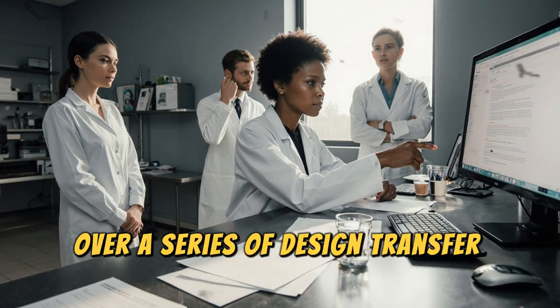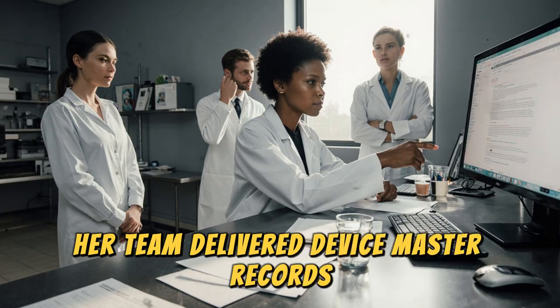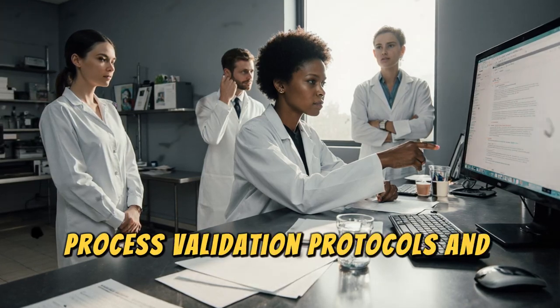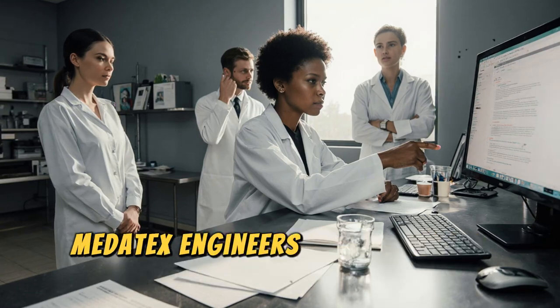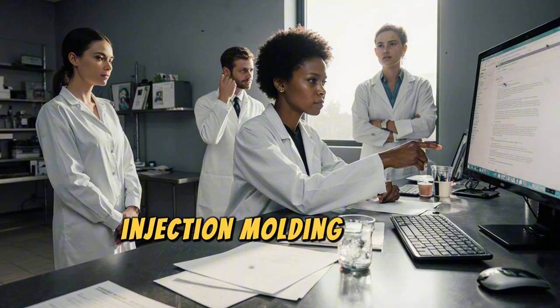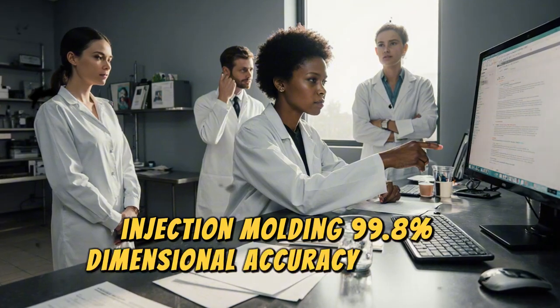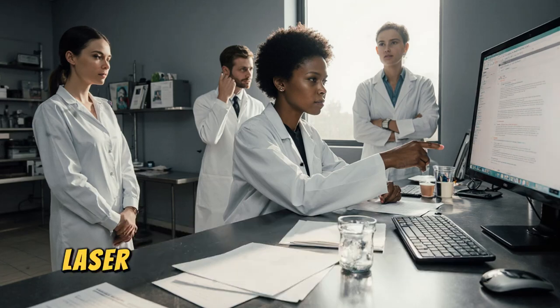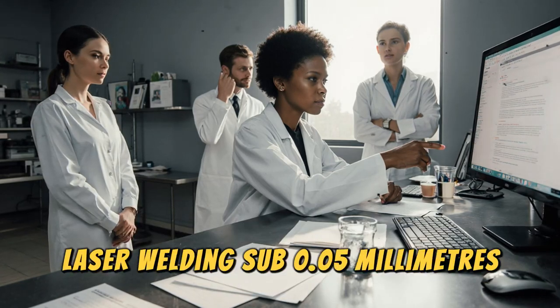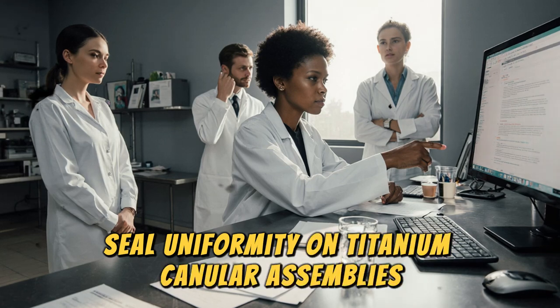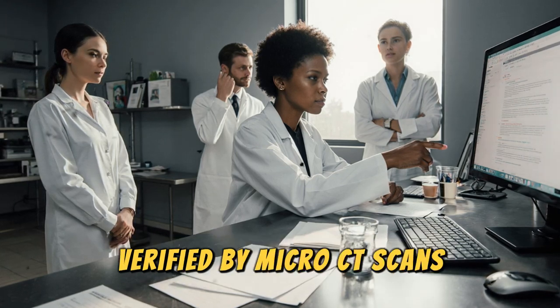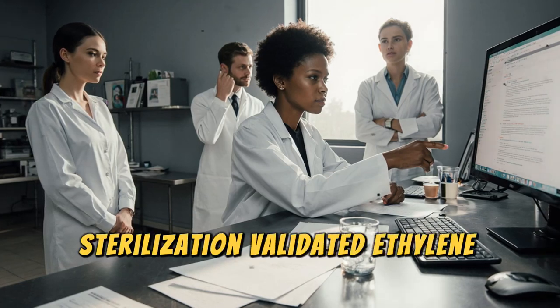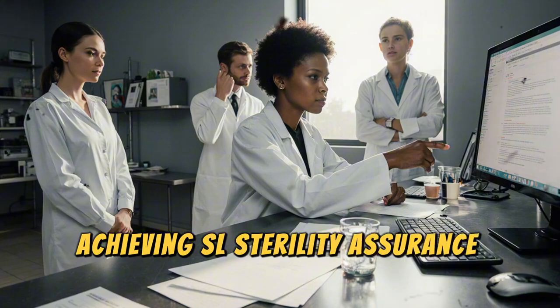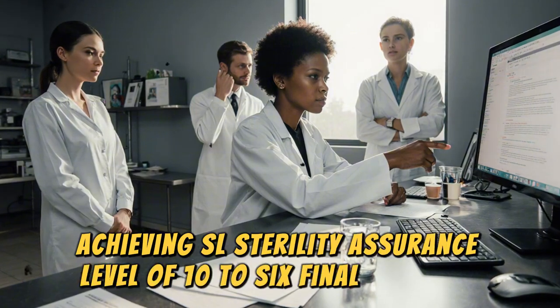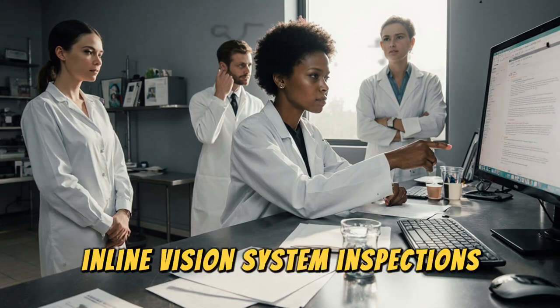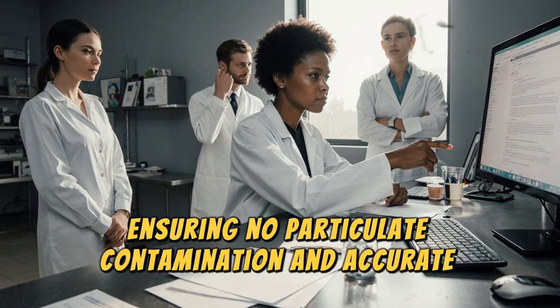Over a series of design transfer workshops, her team delivered device master records, process validation protocols, and control plan documentation. Medatex engineers qualified each production step. Injection molding: 99.8% dimensional accuracy on PDMS reservoirs. Laser welding: sub 0.05 mm seal uniformity on titanium cannula assemblies, verified by micro-CT scans. Sterilization: validated ethylene oxide cycles achieving SAL, sterility assurance level, of 10^-6. Final assembly: inline vision system inspections ensuring no particulate contamination and accurate channel alignment.